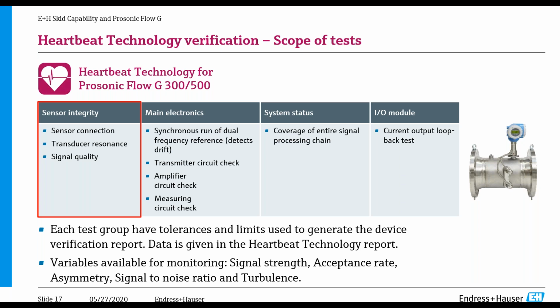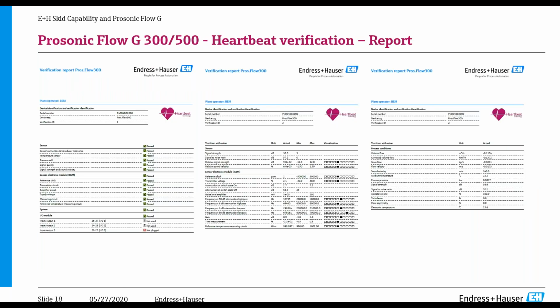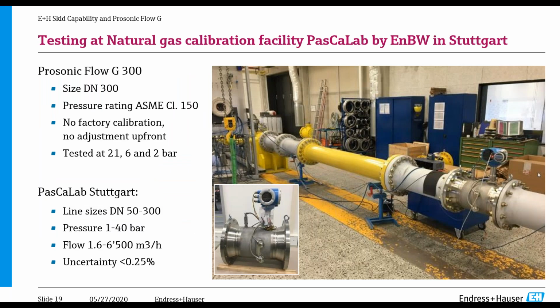We're also doing the standard diagnostics checks and everything. Heartbeat can give you a report, so it's checking your cables, your internal resistances, those type of things. Afterwards, with Heartbeat, you get what we call a Heartbeat Verification report, telling you the health of your meter, if you're good or you're bad, or maybe you need to send it back for recalibration, or what the problem is. That report can also be used for your documentation trail on the device.